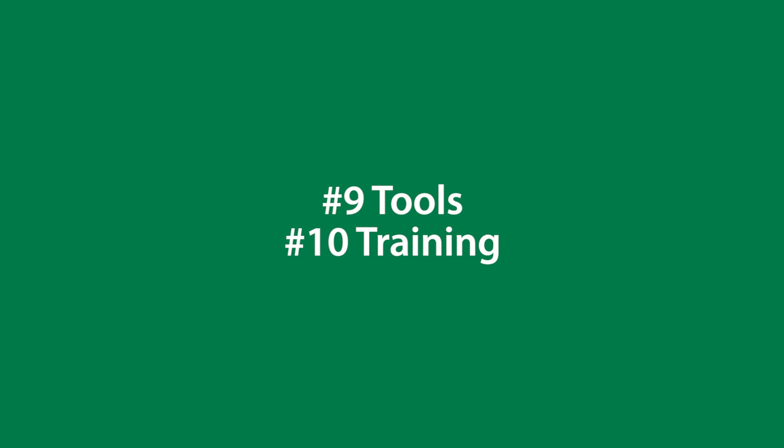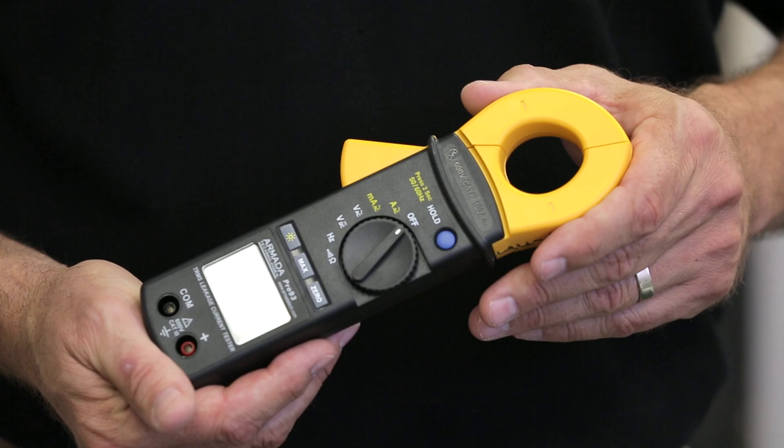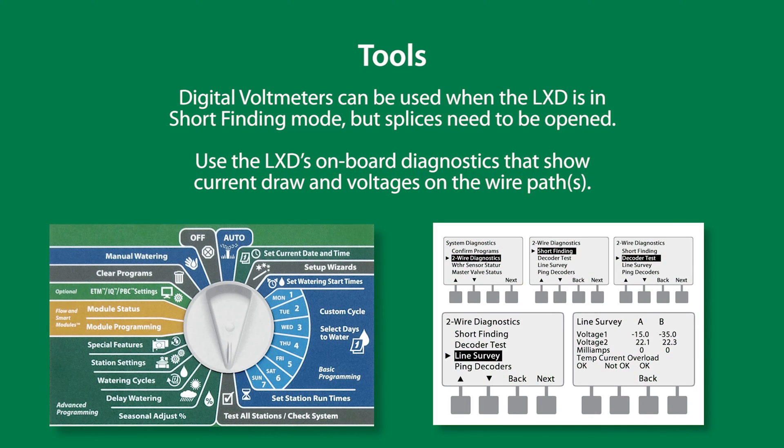Our final part of the series: tools and training. One very important tool needed to work on 2-wire systems is a milliamp clamp meter. Digital volt meters can be used when the LXD is in short-finding mode, but the splices must be opened.